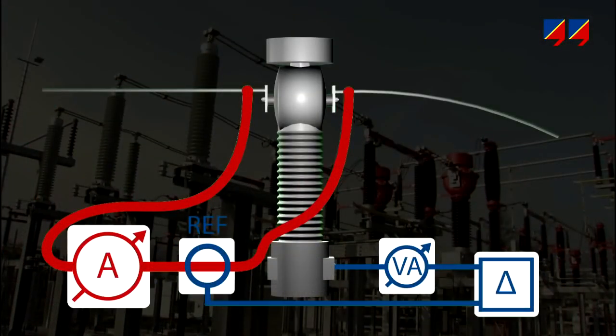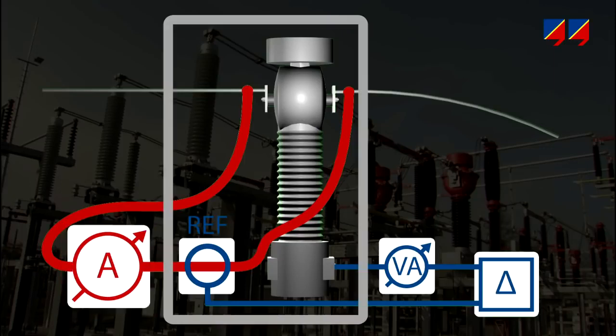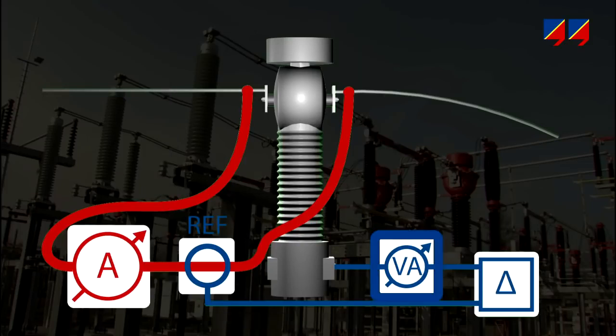If a CT is to be comprehensively tested in a classical manner, the current bridge method is used. Through a high-current source, defined values of primary currents — from fractions to multiples of rated current — are injected into a reference CT and the CT under test, which is connected to a controllable burden box to simulate different load conditions.